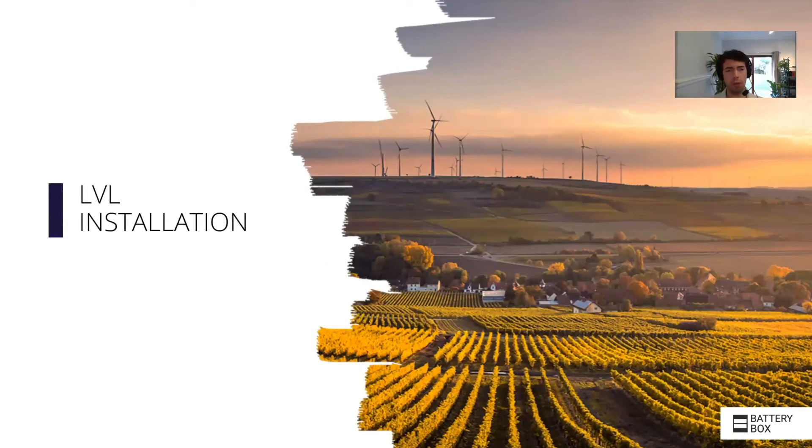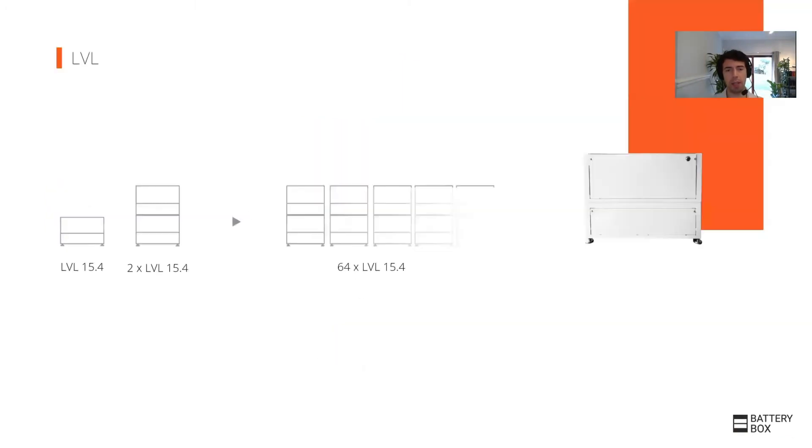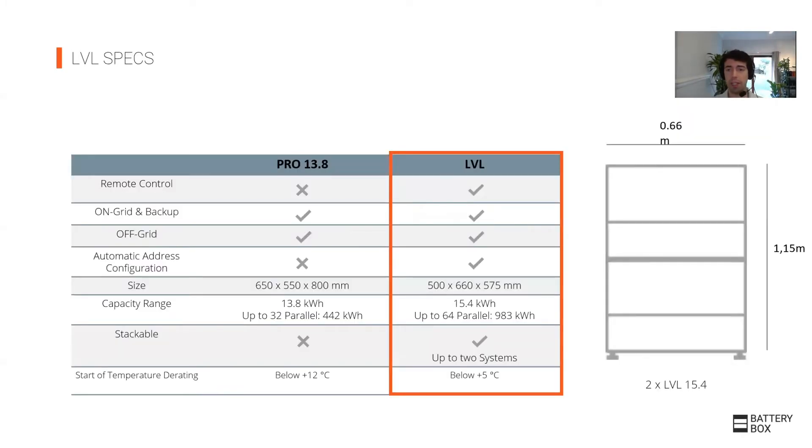Now we go into the low voltage system. The first one is the LVL. The LVL is the most popular system for large commercial units because you can have up to 64 of them in parallel. You're starting from 15.4 kilowatt hours up to 64 kilowatt hours. One of the big features is that you can put one on top of each other, meaning in the size of more or less a washing machine, you could have 30 kilowatt hours of capacity — very compact, especially for large commercial systems. In less space than a 40-foot container, you could have up to a megawatt hour of capacity.